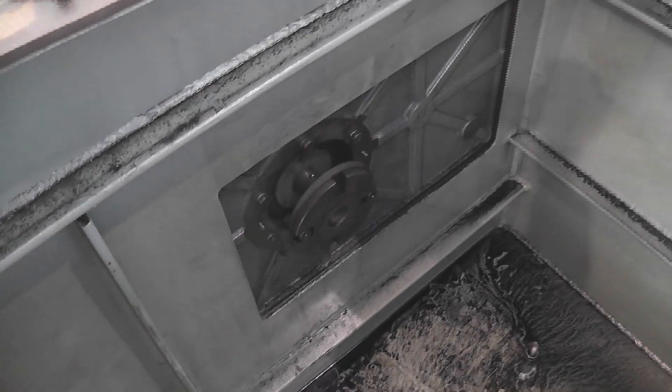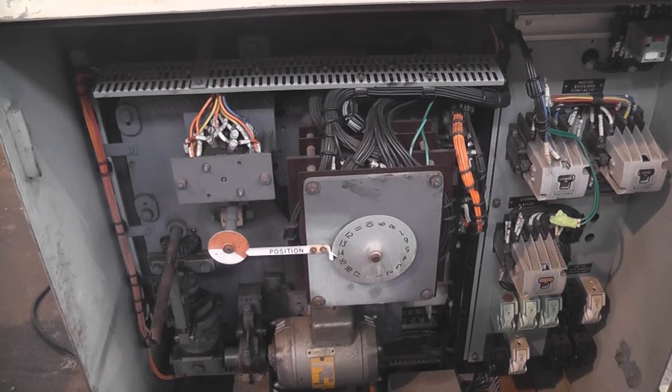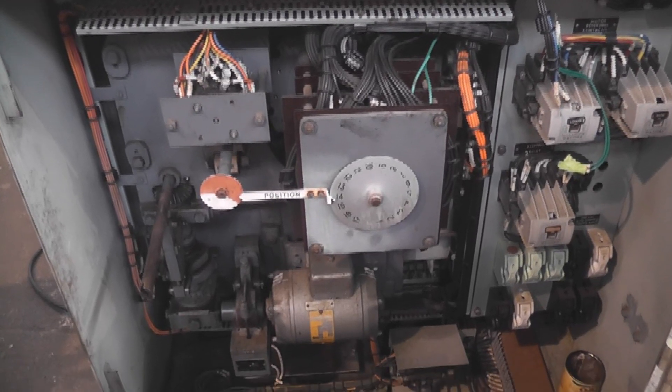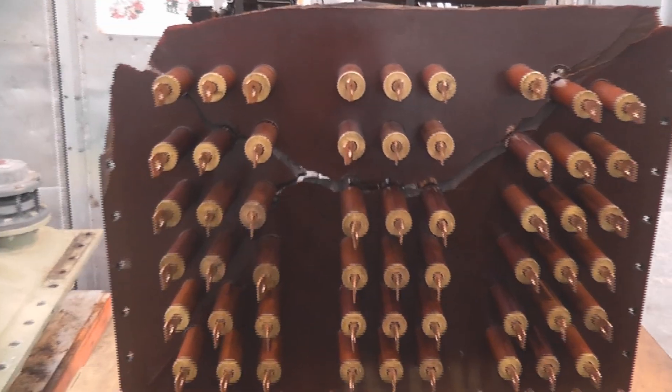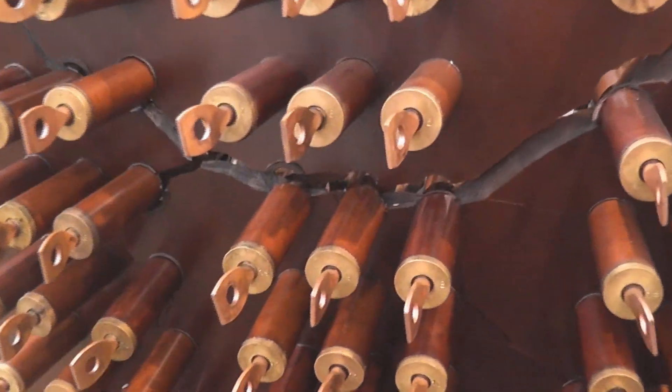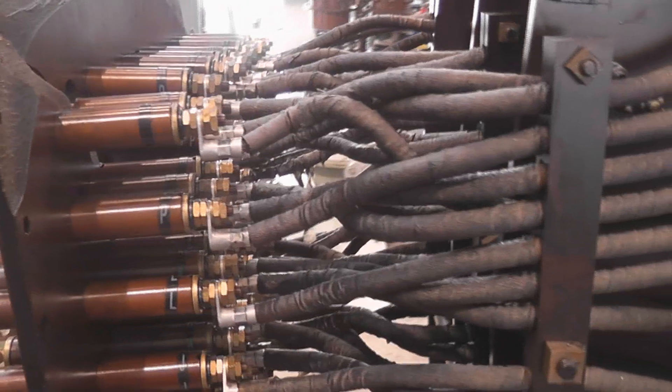We had a fault on the tap changer — a little blast out of here. That's the drive, that's the control side. Here we have the connections and the base plate has cracked. We had a flashover somehow.